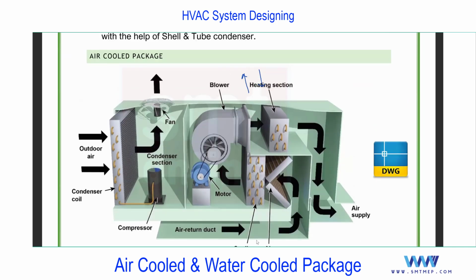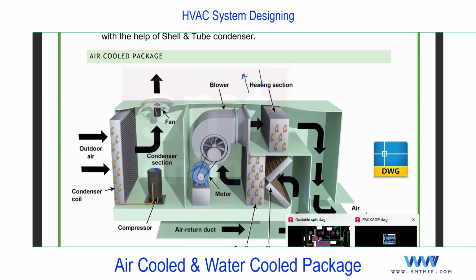Achha, one more point. Remember, when we connect this duct, this supply duct or return duct, since this is partly inside and partly outside, this duct which is outside the building, you must cover with insulation. Even inside the building also, above the false ceiling, we are using the insulation. But in some projects, you will not find the insulation inside the building. But as per standard, the complete duct, supply and return, with insulation.